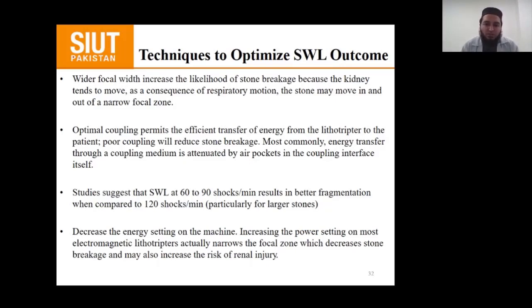As we have already discussed, coupling should be proper and there should not be any air specks in the gel that should be applied over the generator head. Most commonly, energy transfer through a coupling medium is attenuated by air pockets in the coupling interface itself. Studies suggest that shockwave lithotripsy at 60 to 90 shocks per minute results in better fragmentation when compared to 120 shocks per minute, particularly for larger stones.